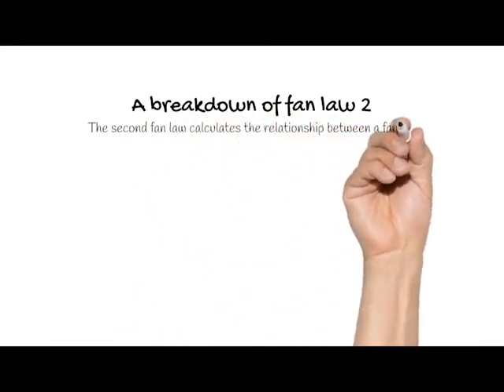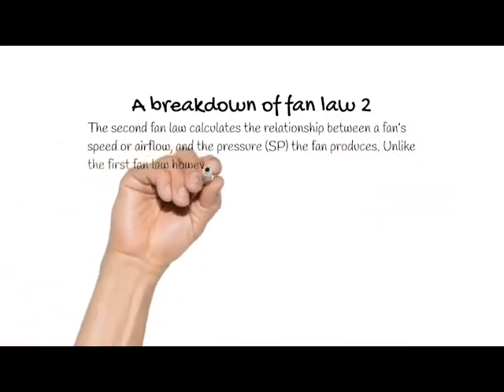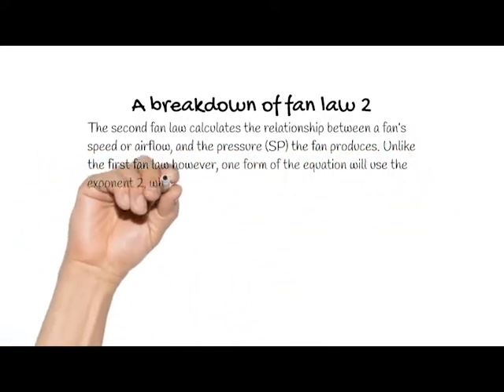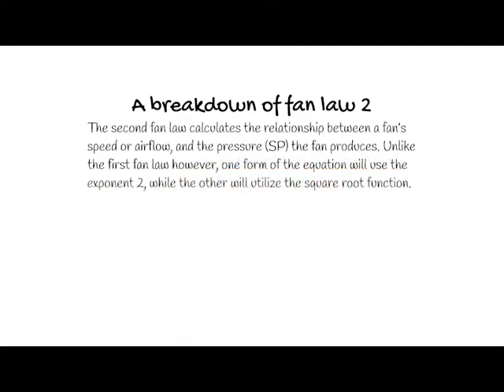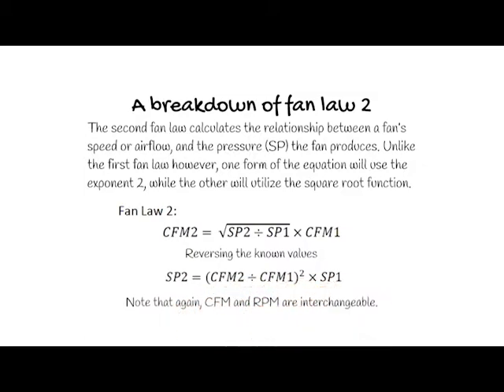Moving on to fan law 2. The second fan law calculates the relationship between a fan's speed or airflow and the pressure the fan produces. Unlike the first fan law, however, one form of the equation will use the exponent 2, while the other will utilize the square root function. Fan law 2 states CFM2 equals the square root of (static pressure 2 divided by static pressure 1), multiplied by CFM1. If we reverse the known values, static pressure 2 equals (CFM2 divided by CFM1) squared, multiplied by static pressure 1. Note that CFM and RPM are interchangeable.